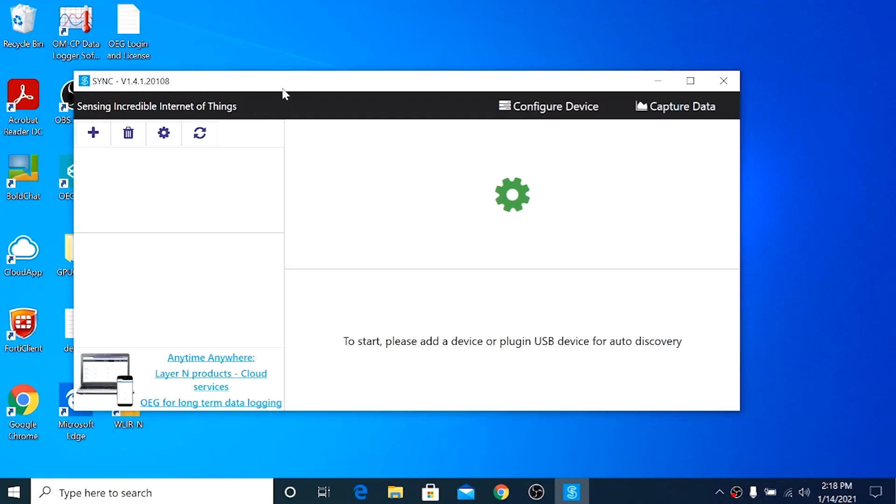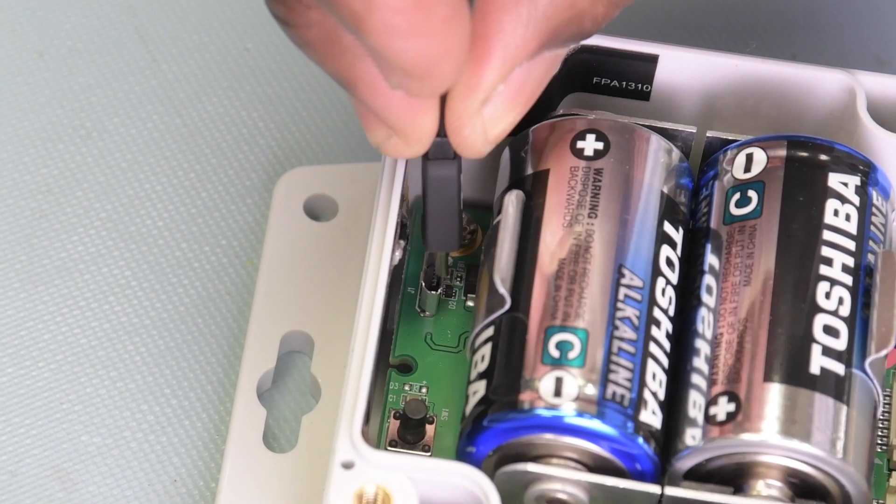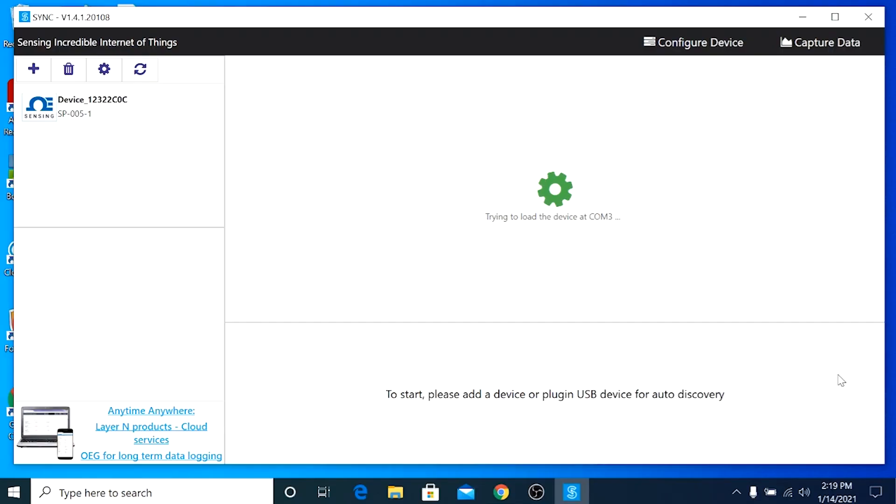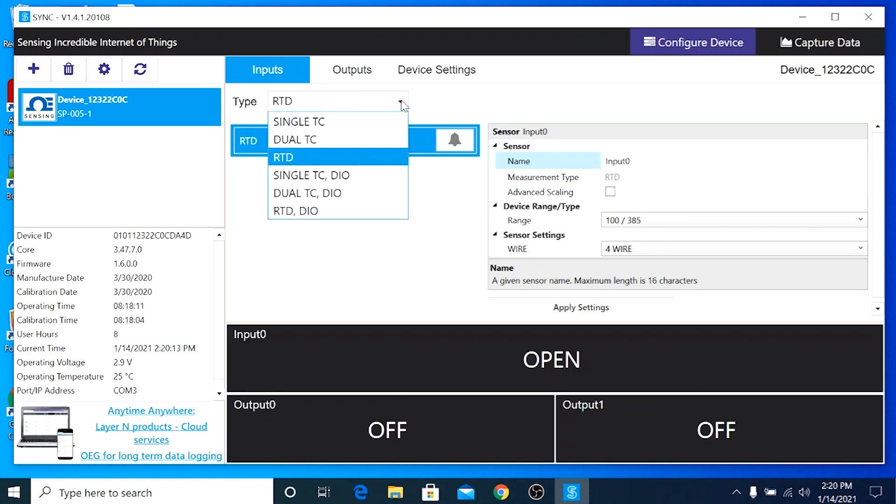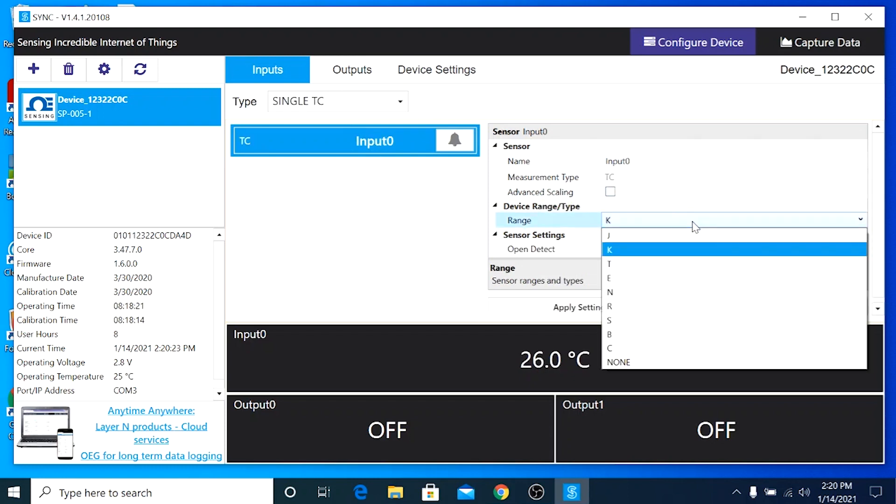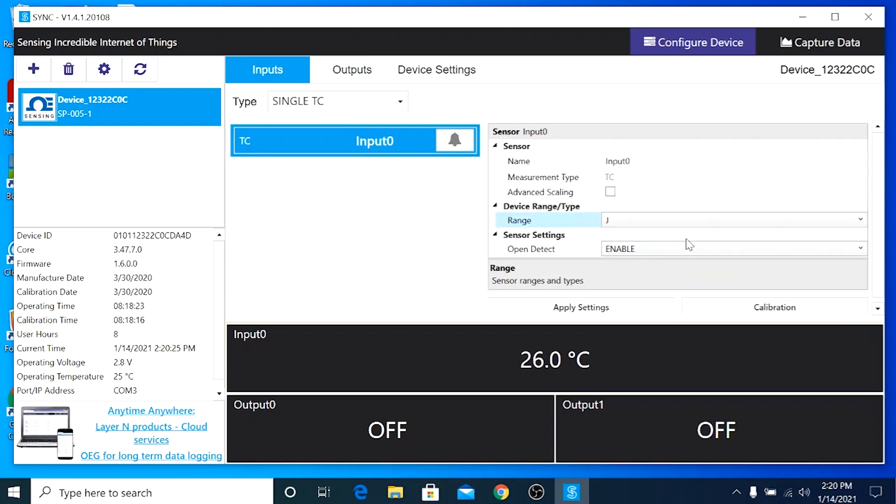Now let's go to the PC and launch the Omega Sync configuration software and connect the micro USB cable to the USB port inside the IF-006 and plug the other end into the PC. Sync will auto detect the smart probe. In the inputs tab, I'll select the type dropdown and choose single thermocouple. And under device range, choose type J since this is a type J thermocouple, then click apply settings. And our smart probe has been configured.